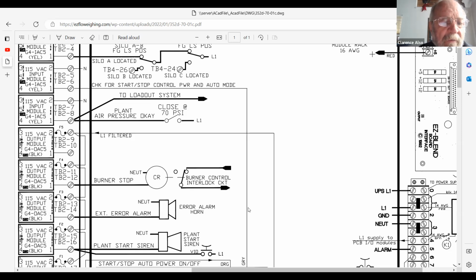And then if you go down to the black, which, oh, okay, this one that says black. And it goes out to some place, L1 filtered. Not sure what that means. Let's go to the next black one below there. That one says burner stop. It looks like you have to have 120 volts there to say stop that burner. And that means that it's going to put 120 volts across that CR coil. And that's the coil of the relay. And you can see the contact.